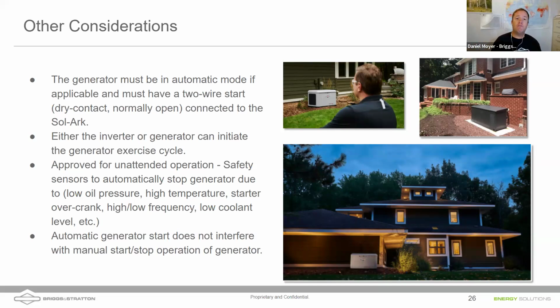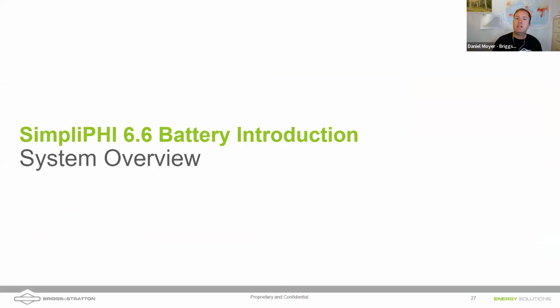Generators do need to be approved for unattended operations, right? So there are some safety features that will shut the generator off if it's not starting. If it's not going to start, it just keeps cranking. Additionally, I would be cautious, and we do have a prime mover disconnect on the generators, that if you're servicing or working on a generator, keep in mind that the inverter is able to start that generator, or the generator itself, due to an exercise cycle. So just keep that in mind as a caution as well.